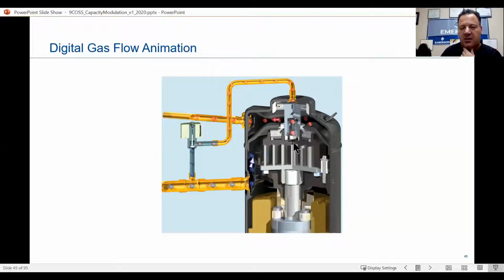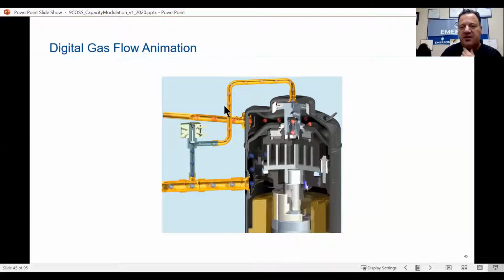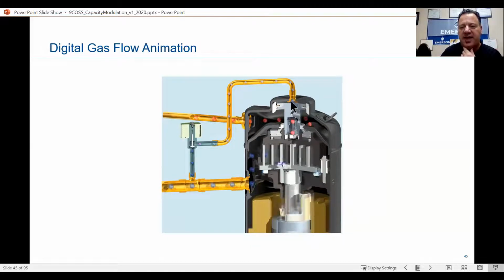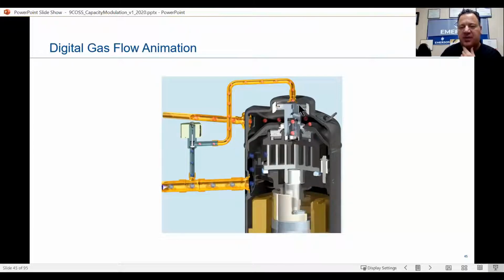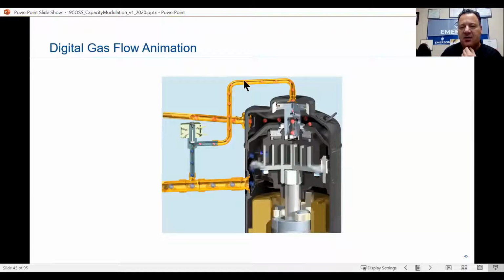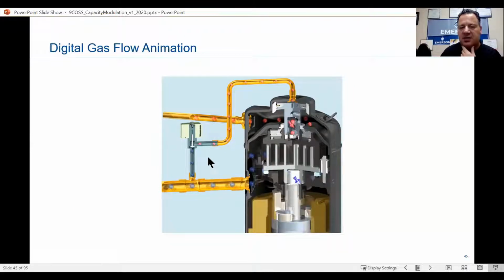It's loaded right now. Notice that when we hit the electric here, okay, now it's charged, it's opened up, and it's bleeding off that gas. Remember those three holes I told you at the top of those plungers that's normally bleeding off a little bit of gas, causing that to push back on the fixed scroll? Well, when this gets opened up, that little bit of gas that's bleeding out through that plunger on the digital, it has nothing to stop it there. So it then bleeds off and into the suction gas, back into the suction gas, okay, mixing with this incoming gas there. So that's the way it works.